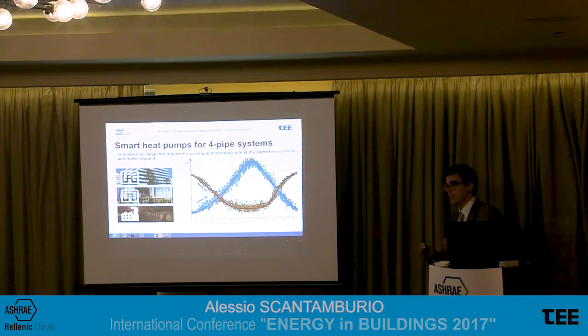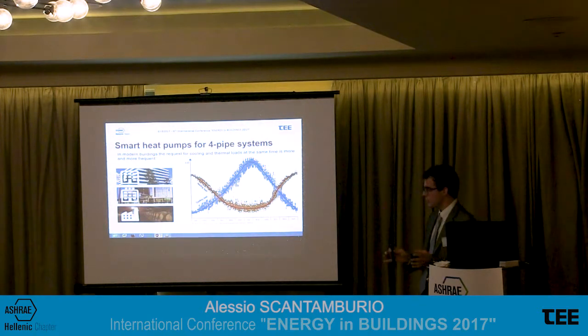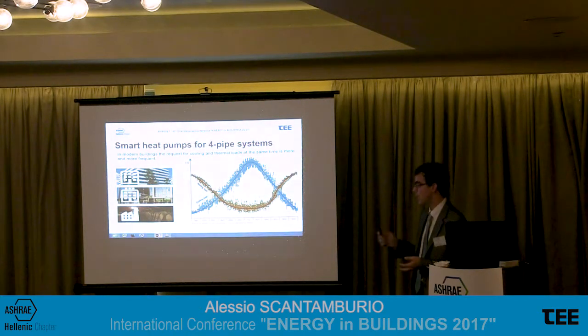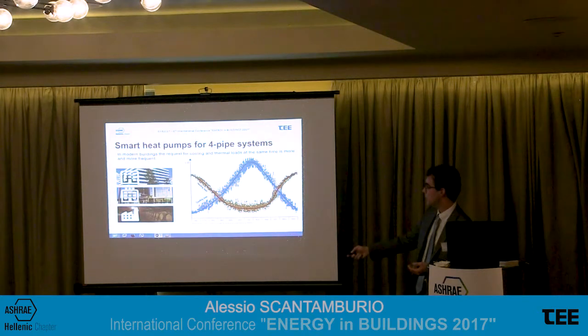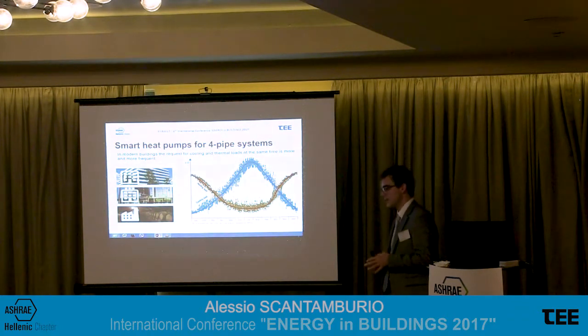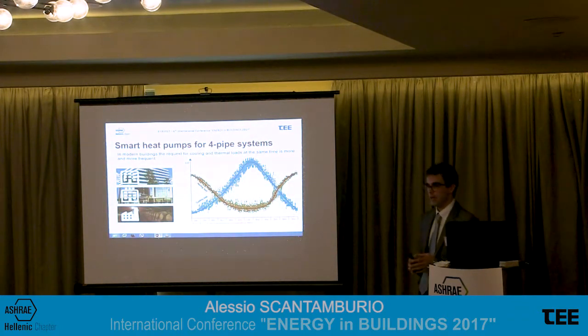Remaining in comfort cooling and heating applications, this could be a simplified thermal profile of a multifunctional complex. We have cooling load, of course, lower during the cold season, and heating load, as opposite, higher. And during the summer season, it is the opposite. So, regarding hydronic plants, how to manage this kind of building?